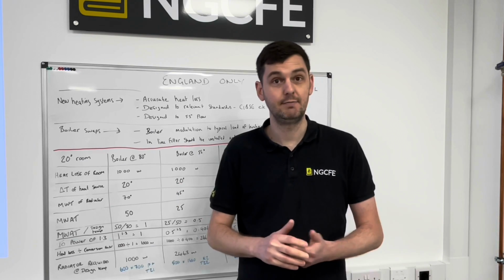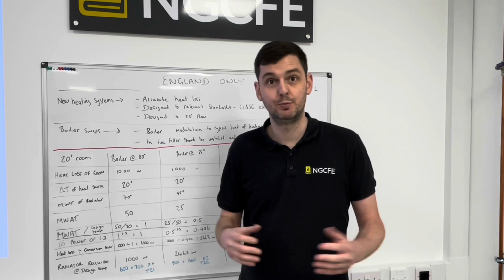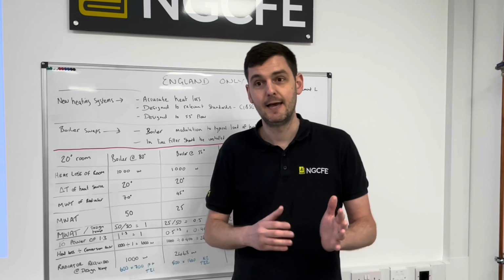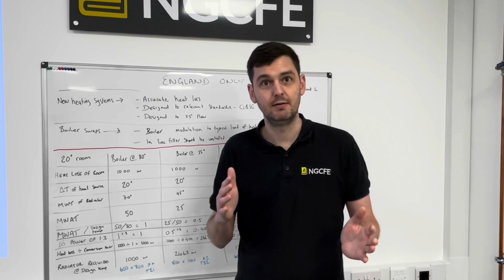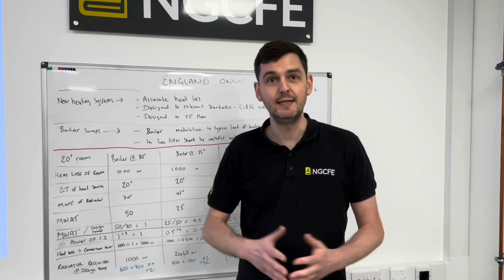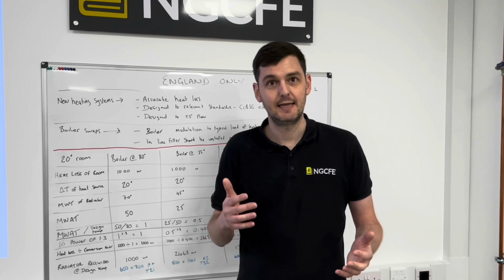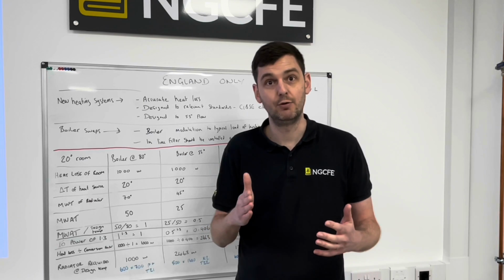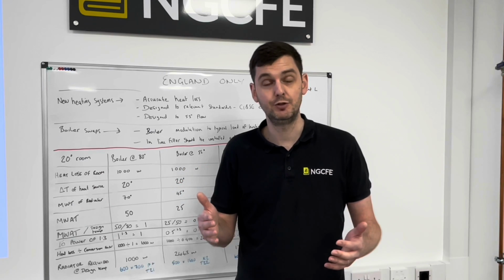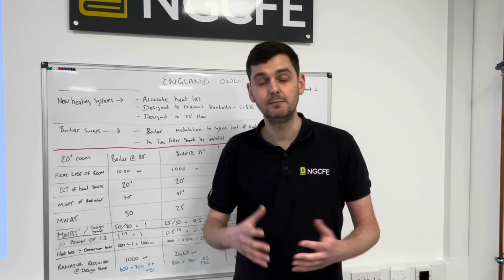If you've got a property, exactly like Alan says, the heat loss is generally designed to the worst possible day outside. So -2.2 degrees up here in Yorkshire, or whatever it may be. So when it's anything warmer than -2.2 outside, you don't need that heat, whether it's 7 kilowatts, 8 kilowatts, whatever it may be. So you need to select a heat source that will modulate down, so that in those warmer times of the year, you're not using gas that you don't need to be using. And we've done a good video on controls and OpenTherm that covered this quite well.